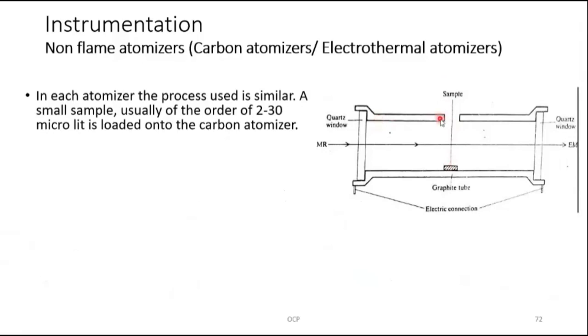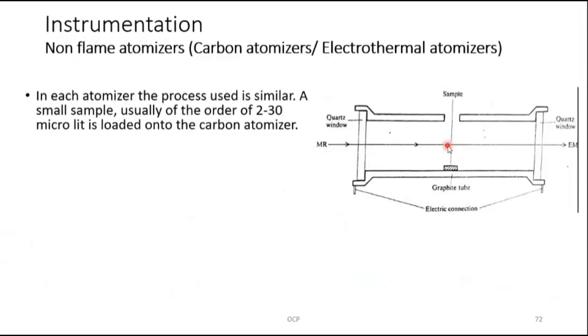Looking at the cross-section of the cylinder: at each end there are quartz windows so that electromagnetic radiation (EMR) can pass through. The graphite tube cylinder is connected to electrical contacts. When electricity passes through it, the graphite heats up, transferring heat to the sample solution, ultimately converting it into atoms.